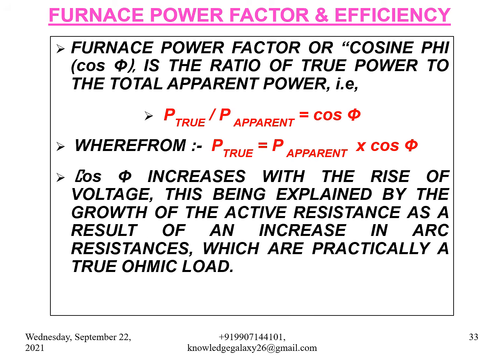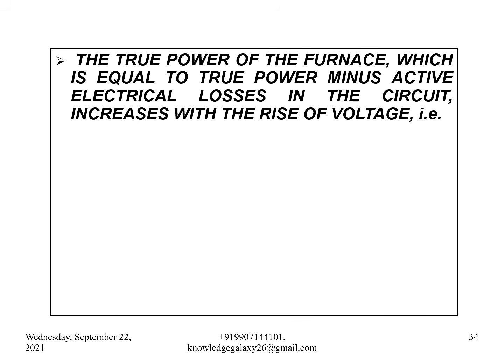Cos phi increases with the rise of voltage, this being explained by the growth of the active resistance as a result of an increase in arc resistances, which are practically a true ohmic load. The effective power of the furnace, which is equal to true power minus active electrical losses in the circuit, increases with the rise of voltage. That is, P effective is equal to P true minus P losses.